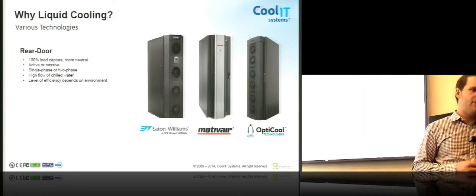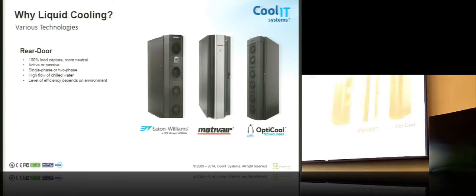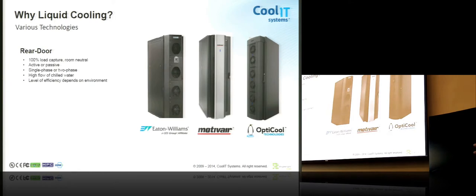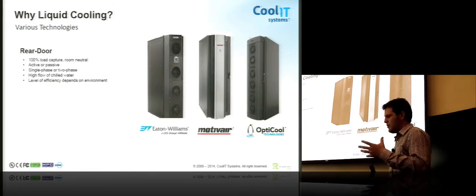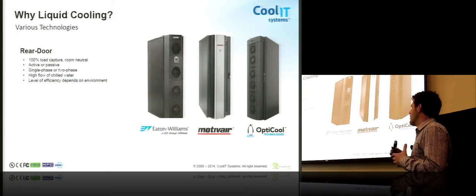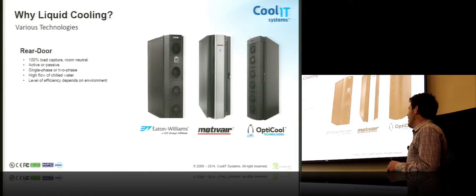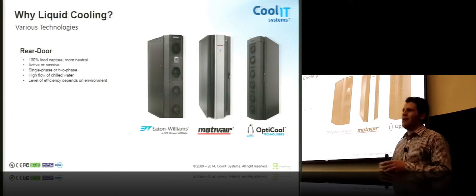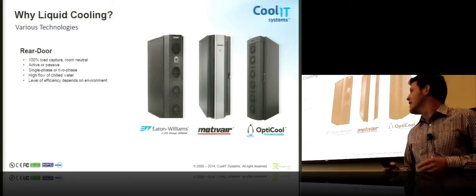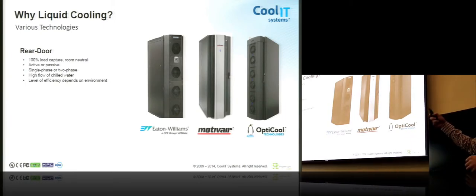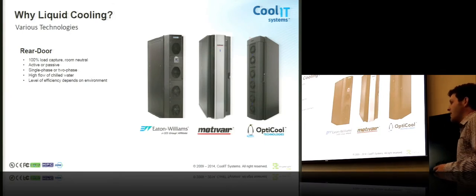The questions that I would have around that are in non-heterogeneous racks. How well does a passive rear door work? In that situation, you may want to have an active rear door. We've heard situations where the switches and their power supplies can overcome the pressure and they're sort of moved out of the way, pigged out of the way by the server fans themselves. The obvious benefit, again, just like immersion to rear door is that it's 100% load capture. It's a room-neutral solution.